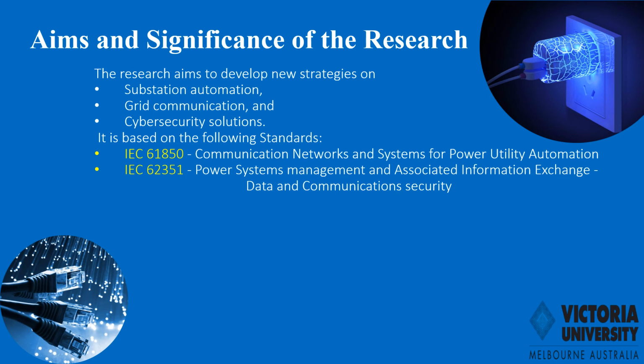The research aims to develop new strategies on power systems. First, we have substation automation, grid communication, and cybersecurity solutions. It is based on the following standards: the IEC 61850 and the IEC 62351. The IEC 61850 covers the communication networks and systems for power utility automation, while the IEC 62351 covers the data and communication security of IEC 61850.